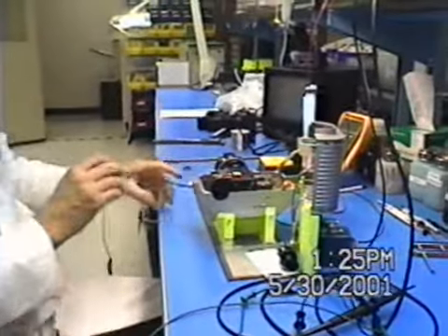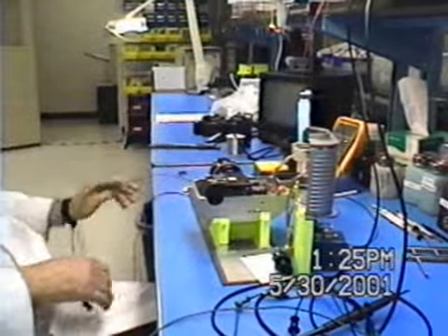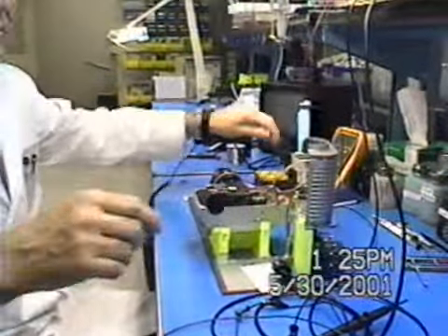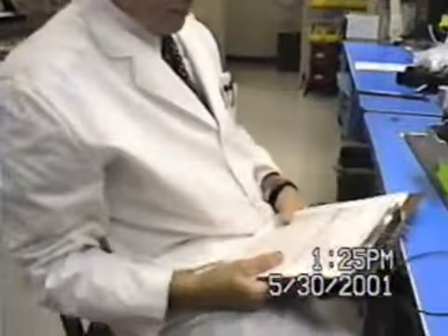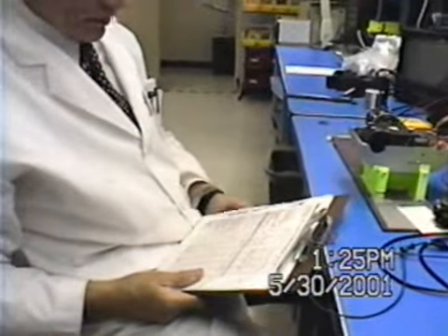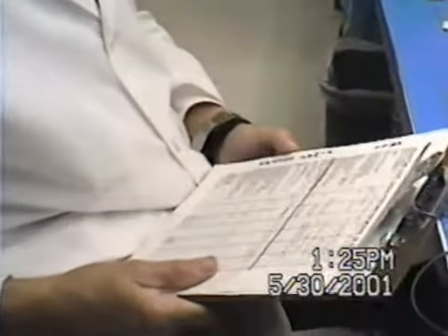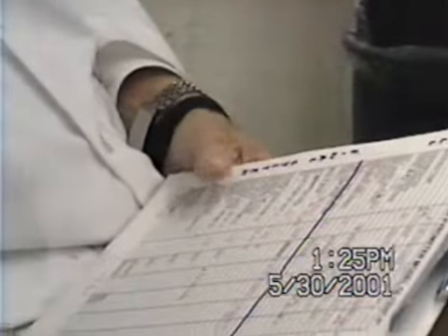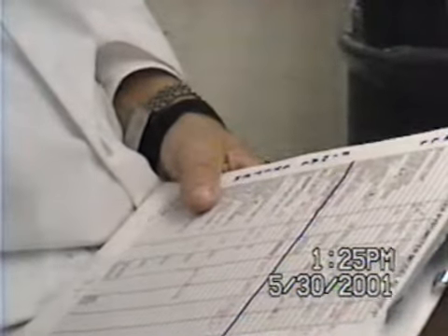We went through the radiance calibration, and we found, let me just get those numbers here from my sheet. We had the black body furnace calibrated to be at 906 centigrade radiance temperature actual, and the display showed 1856 Fahrenheit, 1855 Fahrenheit, excuse me, which is 1013 centigrade. That was for a 10 mega ohm feedback resistor with the pot turned all the way counterclockwise to 0.